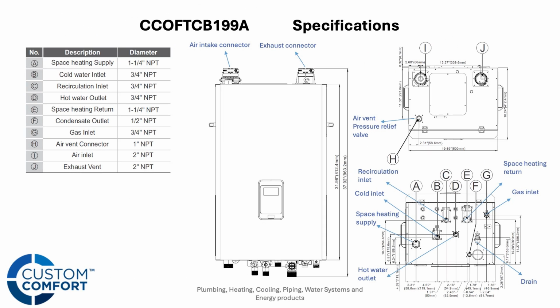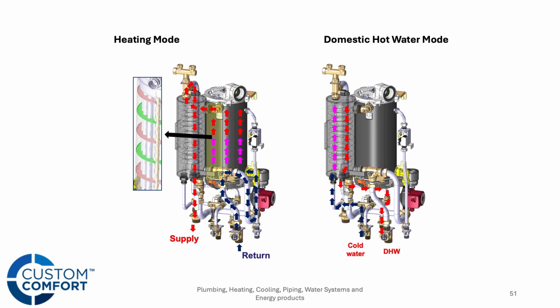Again, just a different view of what we just talked about, but 2-inch venting off the top as well, right? Similar to the other boilers, even though it's 199,000 BTUs, you can still vent this up to 50 feet at 2-inch. So slightly different than the first series boiler, right? That was 60 feet. We're talking 50 feet now, or up to 150 feet at 3-inch if you need to go that far.